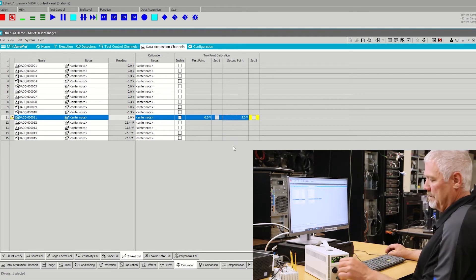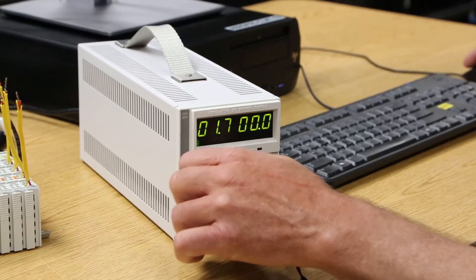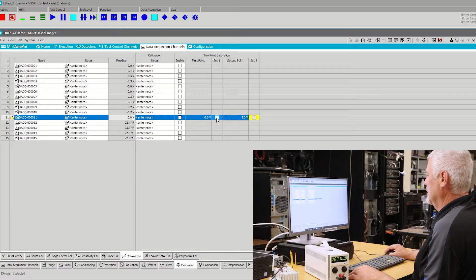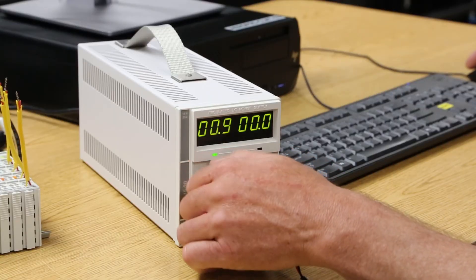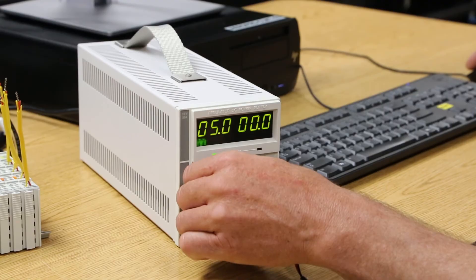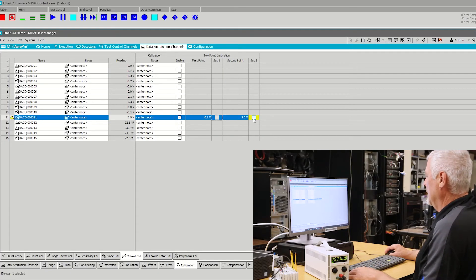At this point, I need to adjust the input to the first point, zero volts, set the point. Now I will set point two by adjusting the input to five volts and applying the second point. At this point, the input is calibrated.